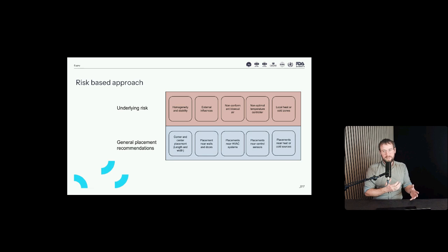So I'm sorry for not giving a yes or no answer, but basically, if you don't need dampeners, you would probably need to be able to justify why air temperature changed without product temperature, and vice versa. If you use dampeners, you need to be able to justify and have the knowledge that the dampening of the temperature sensor is very similar to what the product temperature is. So it's two different kinds of knowledge that you need to have.